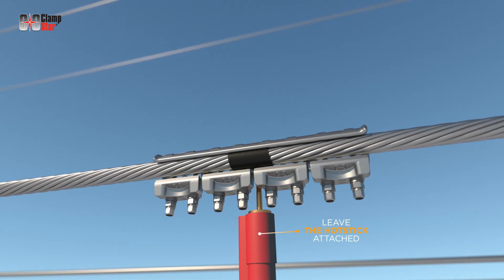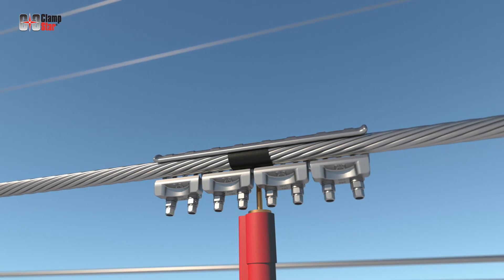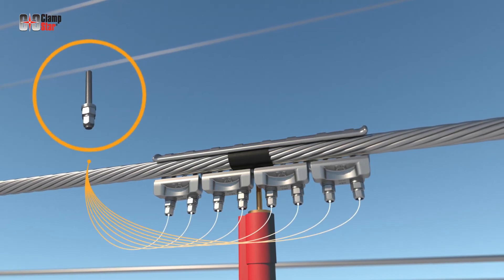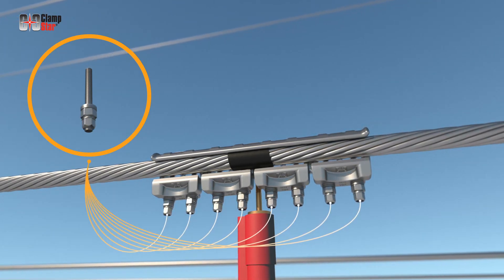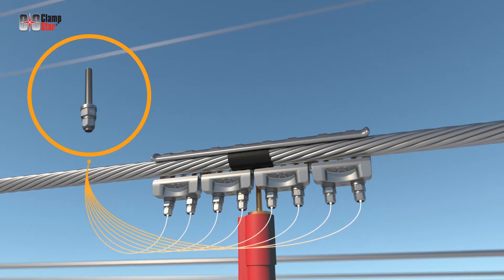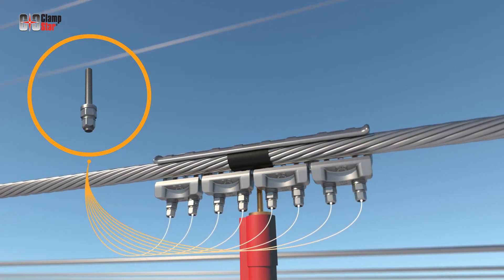Distribution class ClampStar units are supplied with unique nuts designed to shear at the appropriate torque level. The torque limiting nut negates the need for a torque wrench, assures that proper fastener torque is achieved, and also provides inspectors a means to verify proper installation.